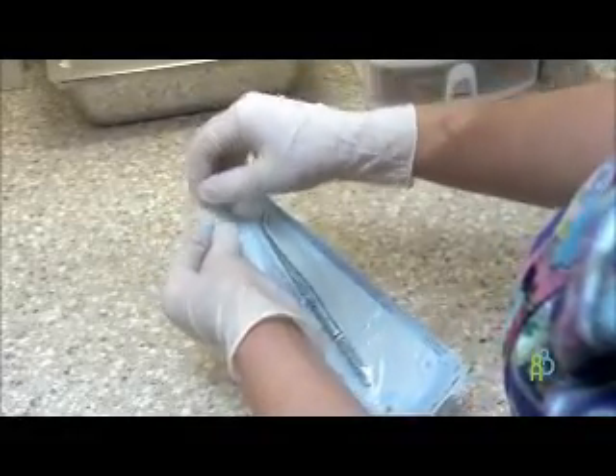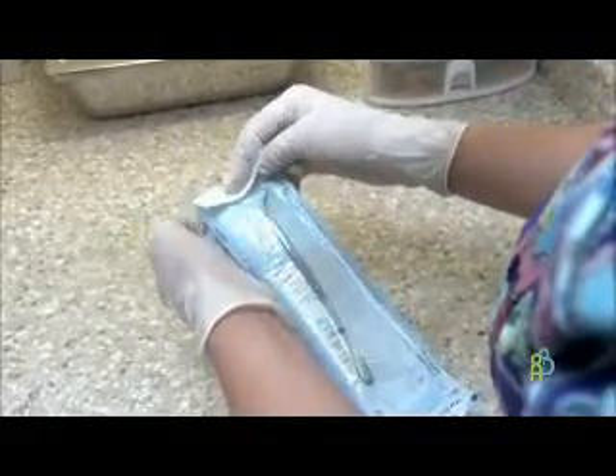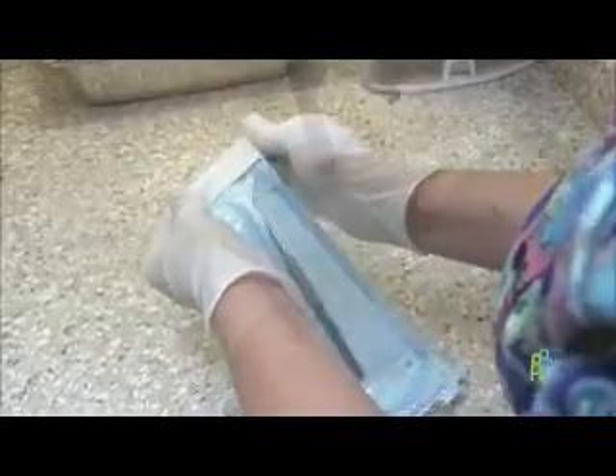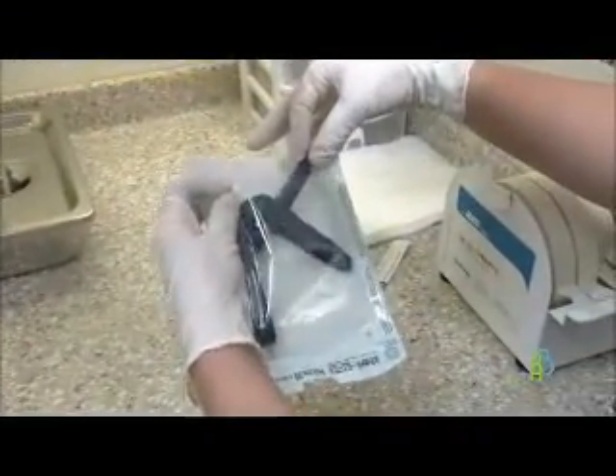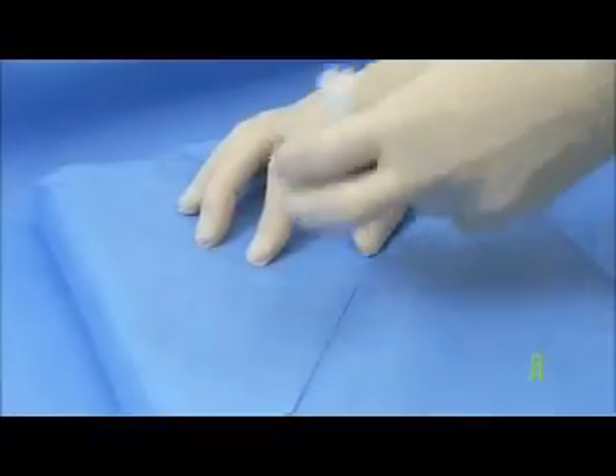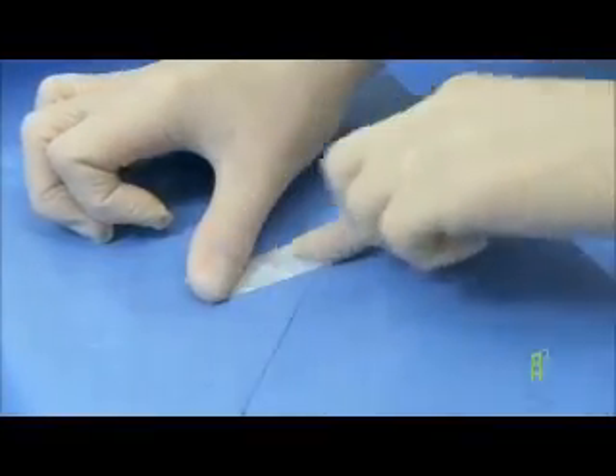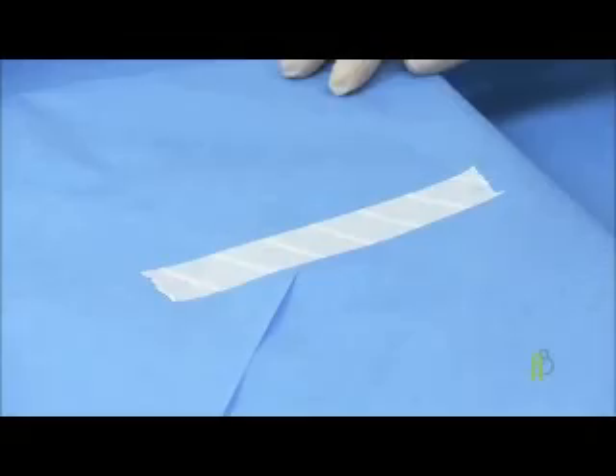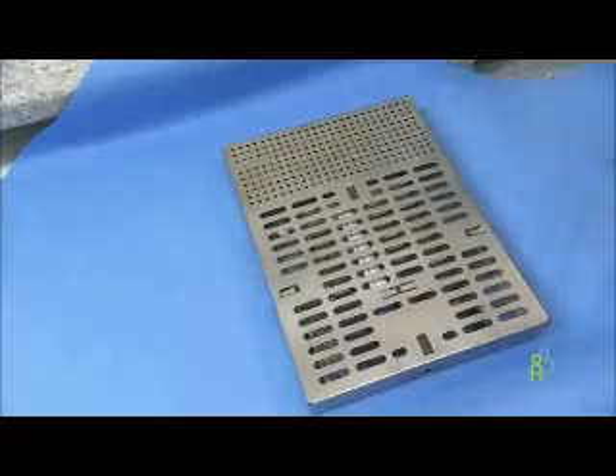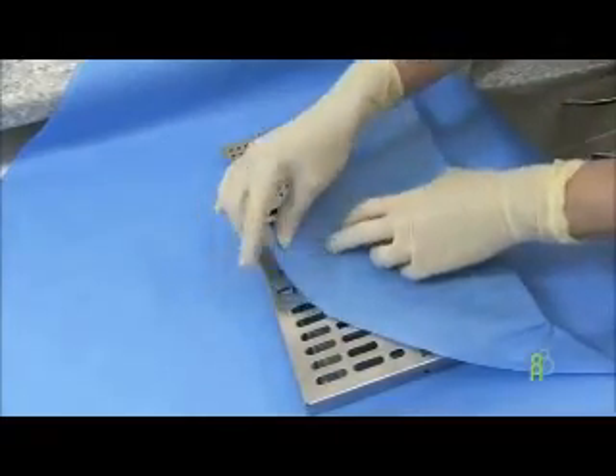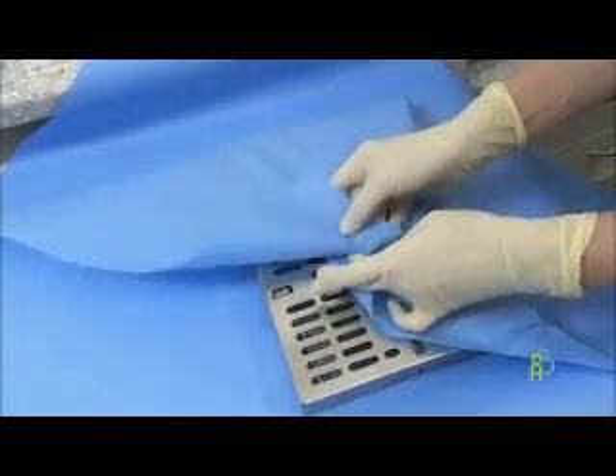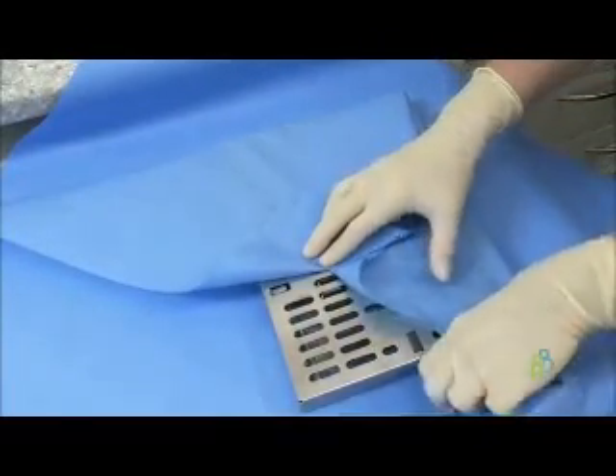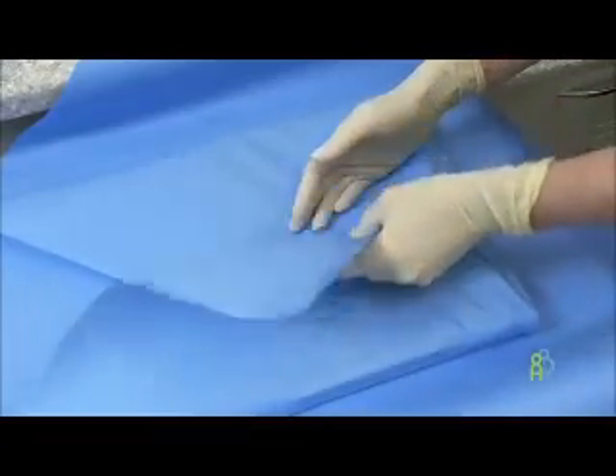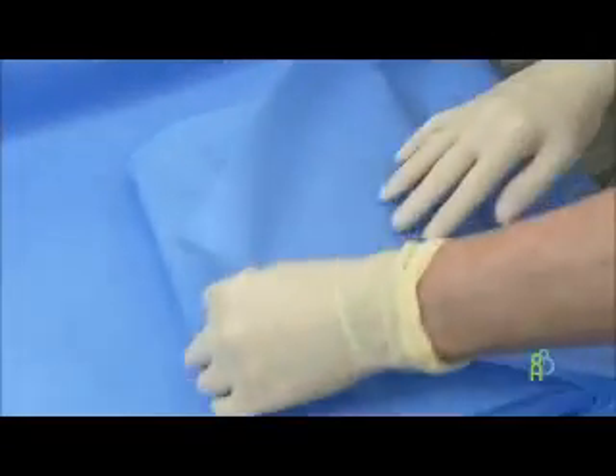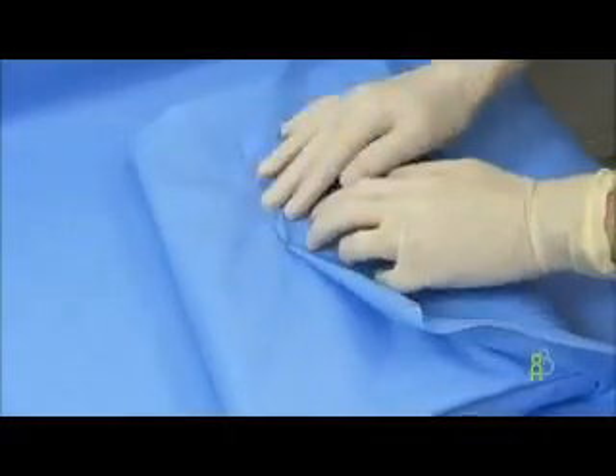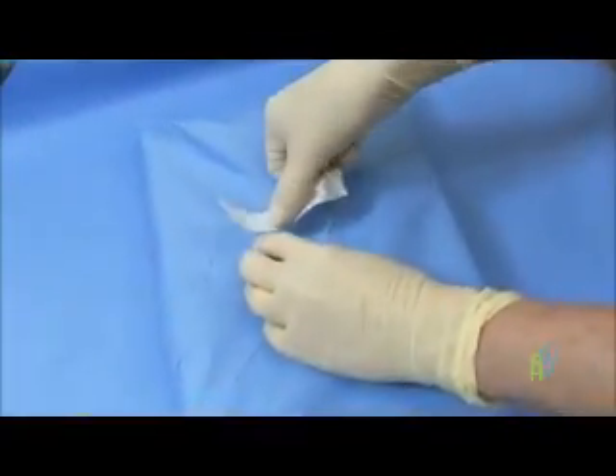All packages must be sealed. Peel pouches must have seals that are smooth and intact. Devices must not place stress on any of the seams or the seal of the peel pouch. Non-woven wrap must be sealed with tape that has been validated by the manufacturer for use in a steam sterilizer. If non-woven wrap is used, it must meet the following requirements. Be flexible enough to permit sealing, wrapping, and unwrapping with minimal memory. Produce no lint or particles. Be resistant to tears, and not leach or deposit toxic substances or non-fast dyes on the product.